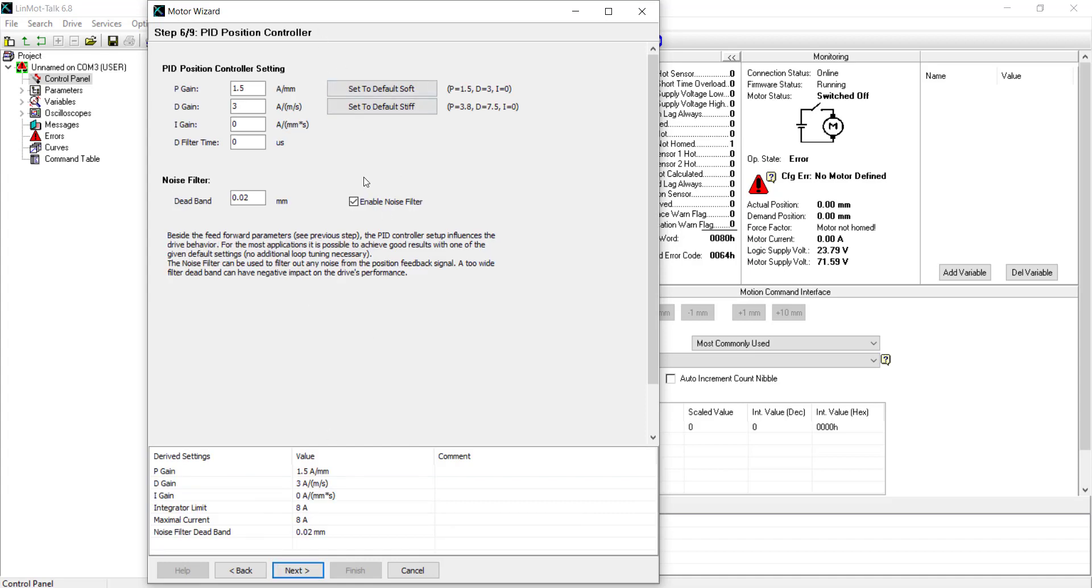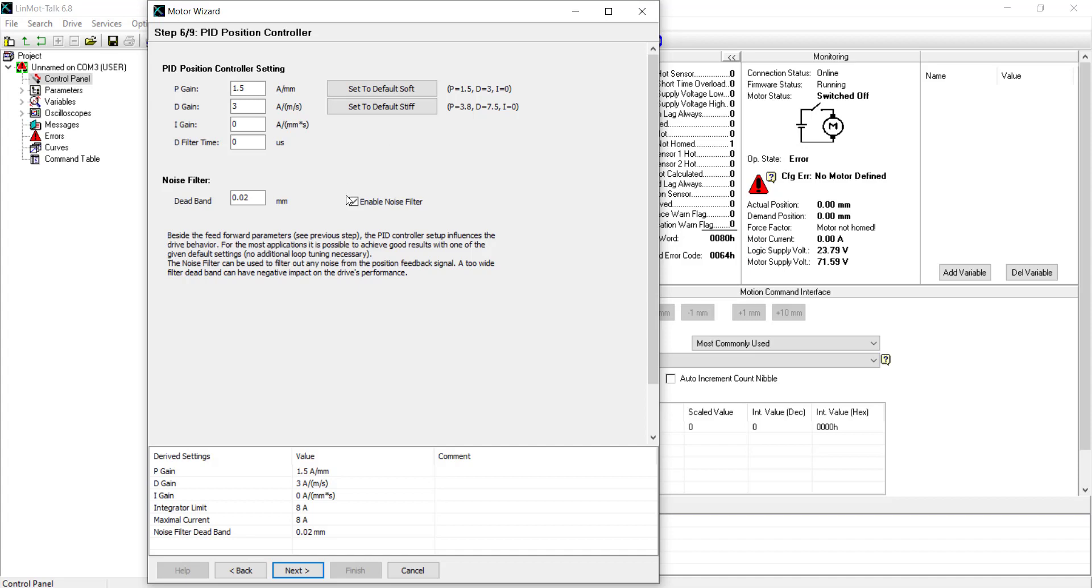Here, we have the PID position controller. It is recommended to start with default soft settings, because the parameters can be changed anytime. With soft parameter settings, PID values will be low. The motor is low noise, and the position is not controlled very stiffly. With stiff parameter settings, has more noise, and more power consumption of the motor. But, the position will be controlled harder. The noise filter option is to reduce the noise from the position feedback sensor at standstill. We will keep this as default, and go next.